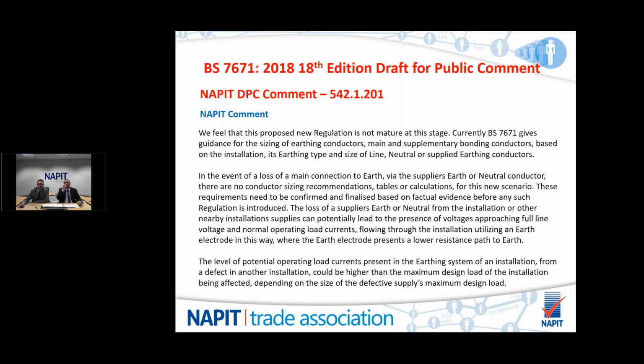We feel this newly proposed regulation is not really mature at this stage. It's been brought about to help out the ENA, the DNOs, where they might have a loss of PEN conductor and they might lose a neutral, which is all very well and good. Currently, 7671 gives guidance on the size of earthing conductors, main and supplementary bonding conductors, etc., based on the installation, earthing type, etc., line, neutral. However, in the event of a loss of a main connection to earth via the supply's earth or neutral conductor, there are no conductor sizing recommendations, tables, calculations, or anything like that for this new scenario.